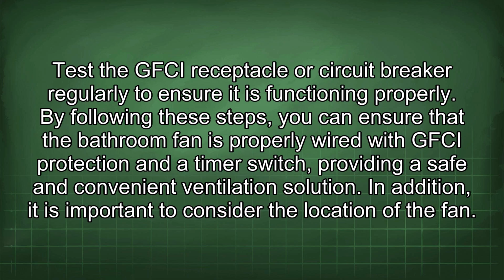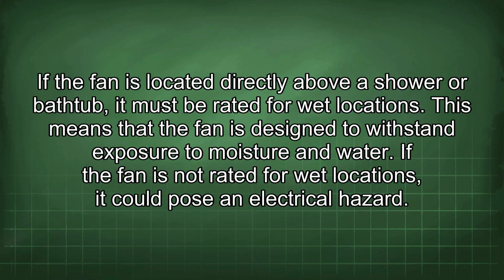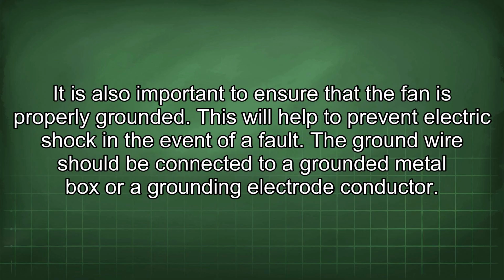In addition, it is important to consider the location of the fan. If the fan is located directly above a shower or bathtub, it must be rated for wet locations. This means that the fan is designed to withstand exposure to moisture and water. If the fan is not rated for wet locations, it could pose an electrical hazard. It is also important to ensure that the fan is properly grounded. This will help to prevent electric shock in the event of a fault. The ground wire should be connected to a grounded metal box or a grounding electrode conductor.